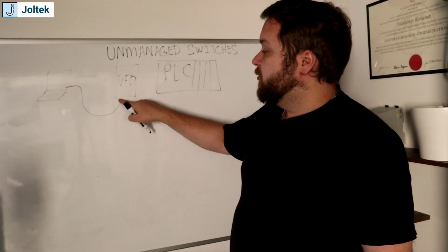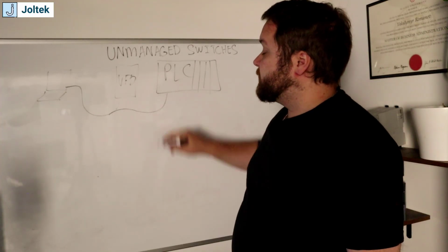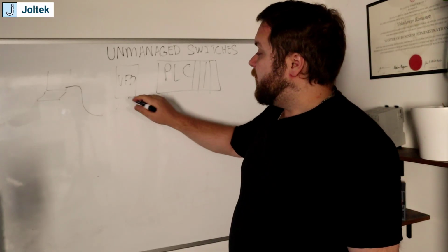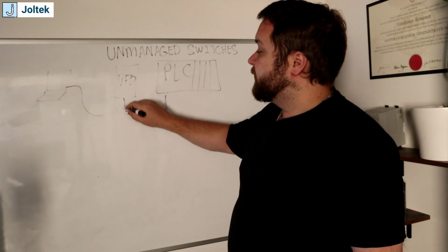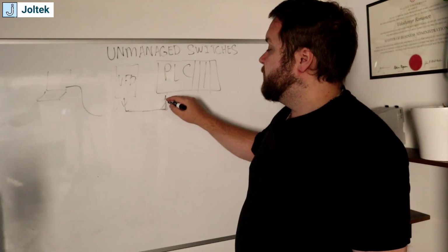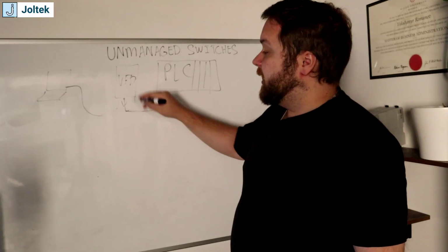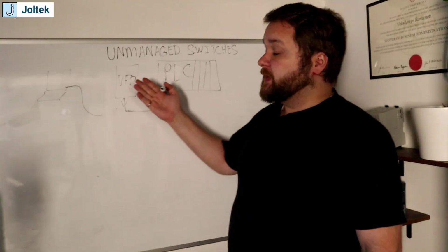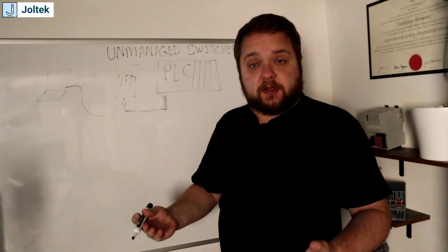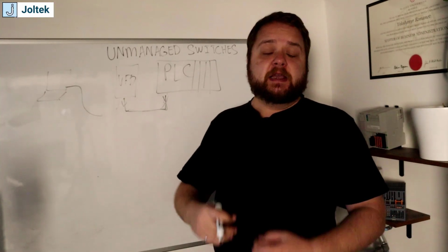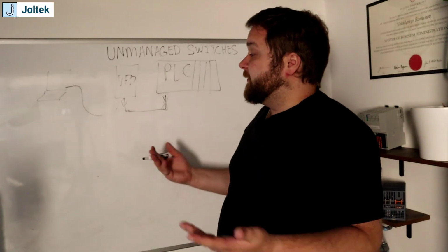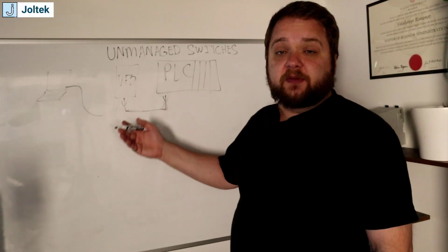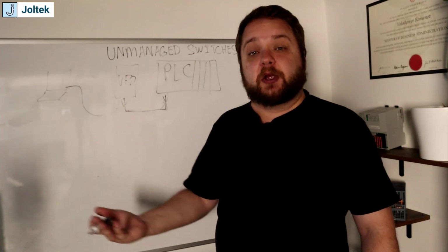So let's imagine that there's going to be a couple of cards going into the field. So I can basically move my laptop then to configure the IP address of the PLC. Once I'm done, I can simply put the cable between those two devices, and the PLC can now communicate to the VFD, so we're going to basically have two-way communication of data over that specific network, and the PLC can stop the VFD over Ethernet. It can also adjust the speed, it can adjust the parameters, and this is perfectly fine, right? So this is going to be the most basic application. Sometimes instead of the VFD, perhaps you have a PLC and an HMI combo.